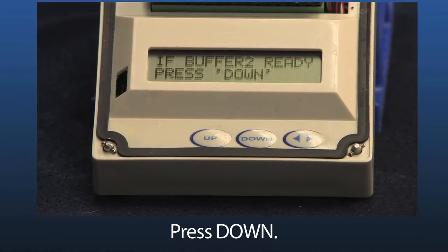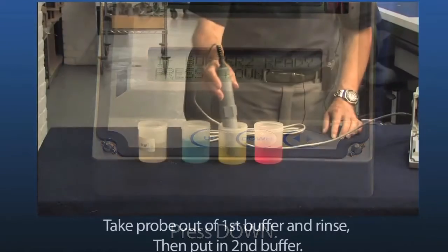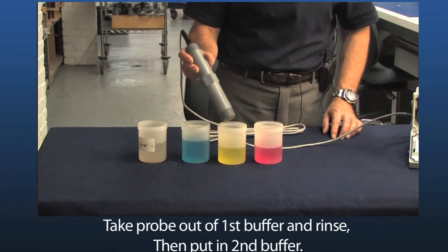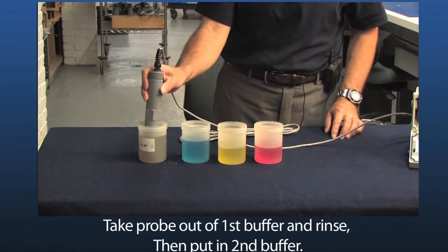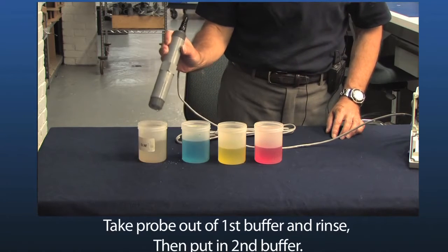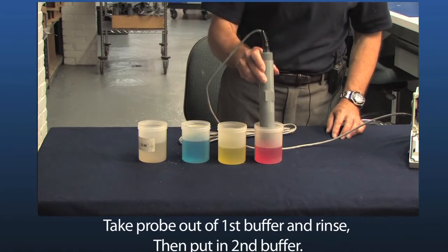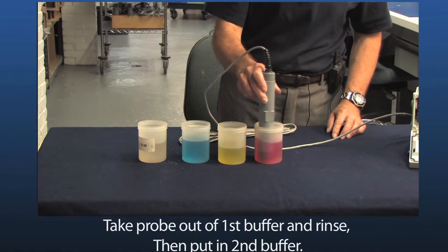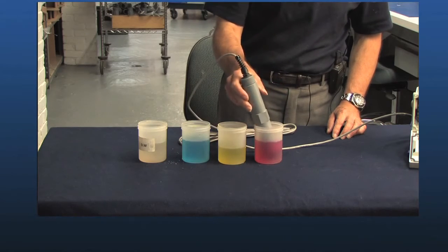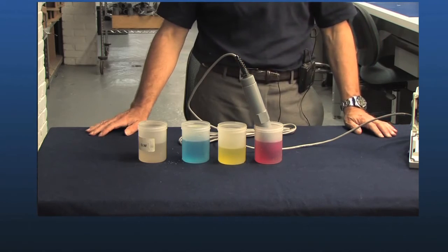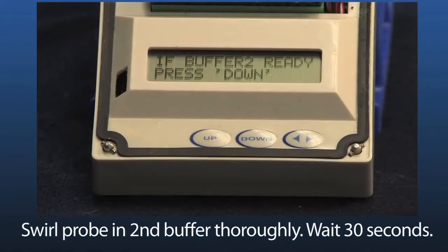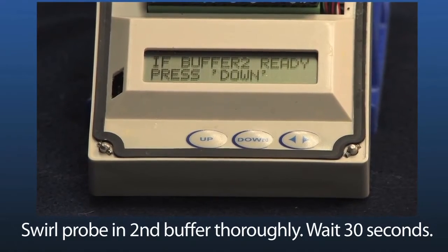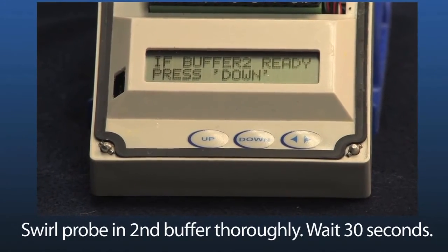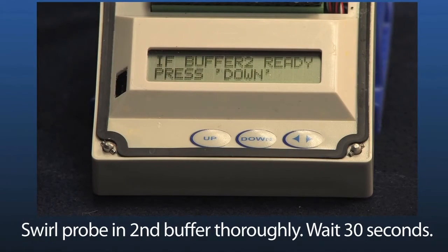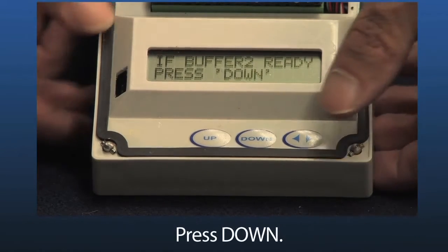Well, buffer 2 is not ready. First thing I have to do is take the probe out of buffer 1, which is pH 7, rinse it out really thoroughly, and then put the probe in my second buffer, which is pH 4. As before, I'm going to swirl the probe around in the calibration solution very thoroughly so that I get a really good flow across the process electrode. I'm going to wait at least 30 seconds, and then when I'm ready, I'm going to press down.